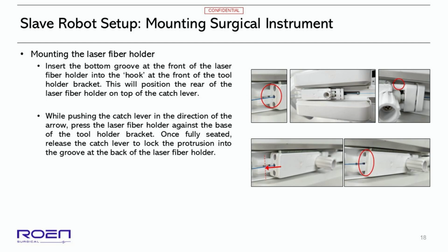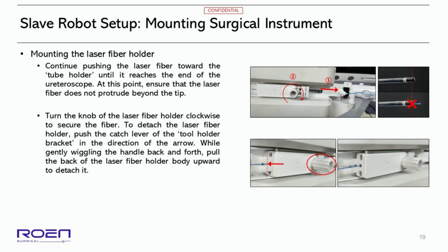While pushing the catch lever in the direction of the arrow, press the laser fiber holder against the base of the tool holder bracket. Once fully seated, release the catch lever to lock the protrusion into the groove at the back of the laser fiber holder. Continue pushing the laser fiber toward the tube holder until it reaches the end of the ureteroscope. At this point, ensure that the laser fiber does not protrude beyond the tip. Turn the knob of the laser fiber holder clockwise to secure the fiber.